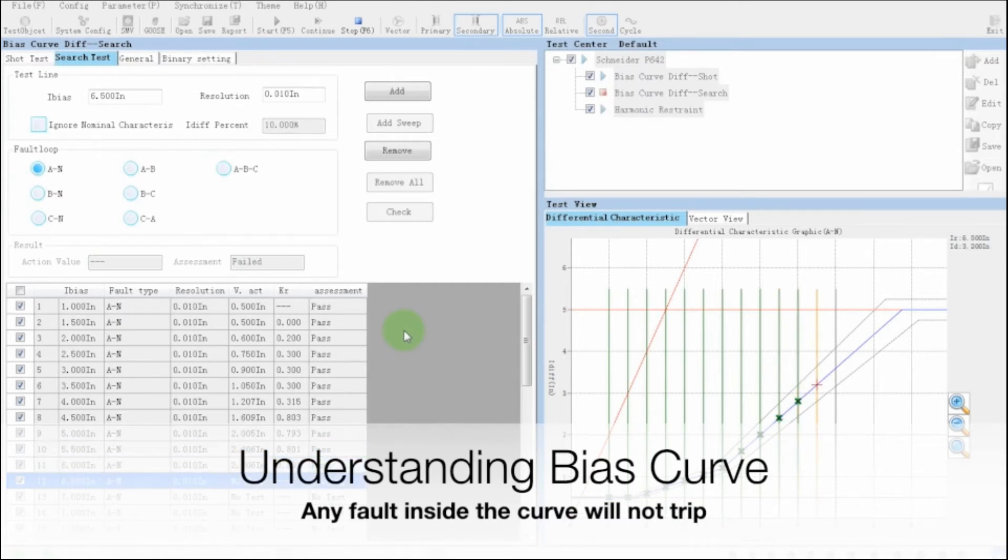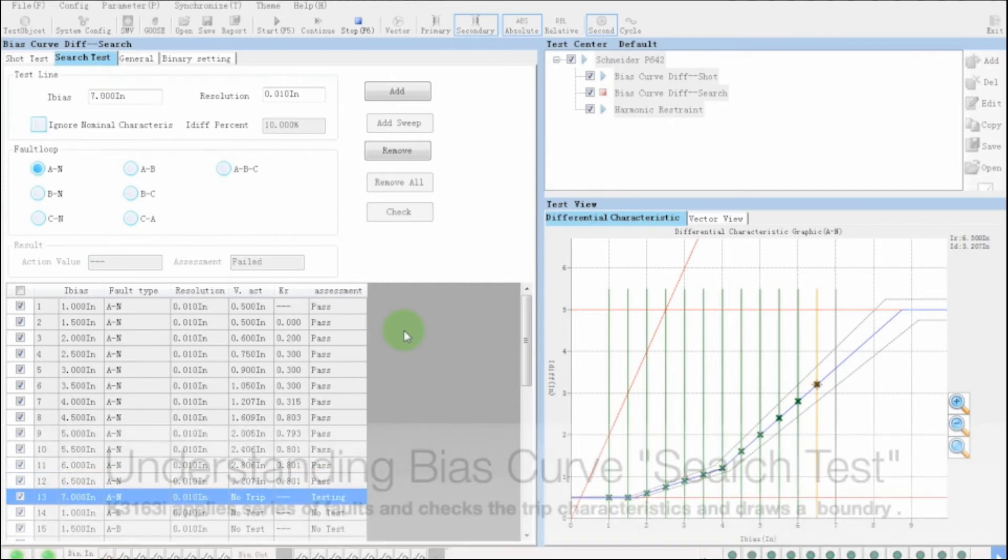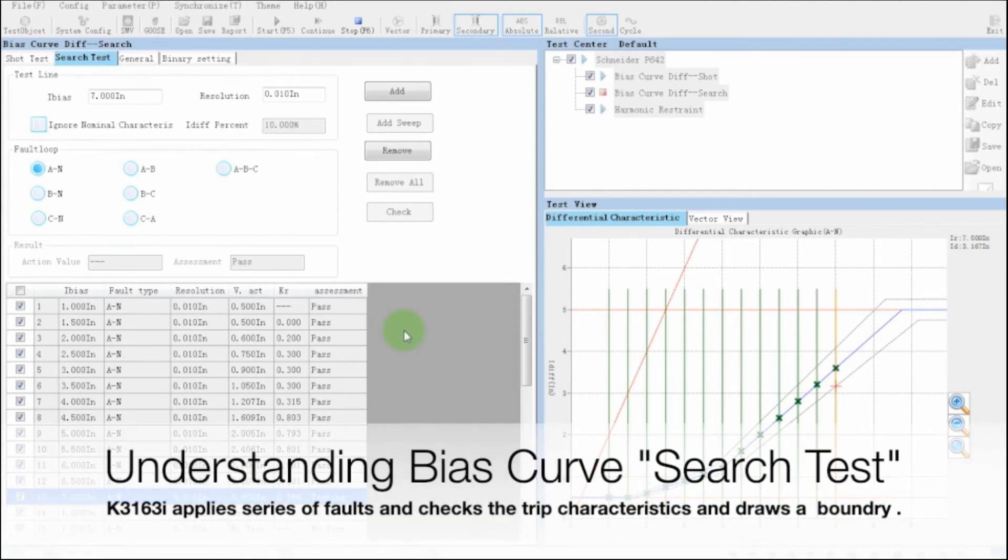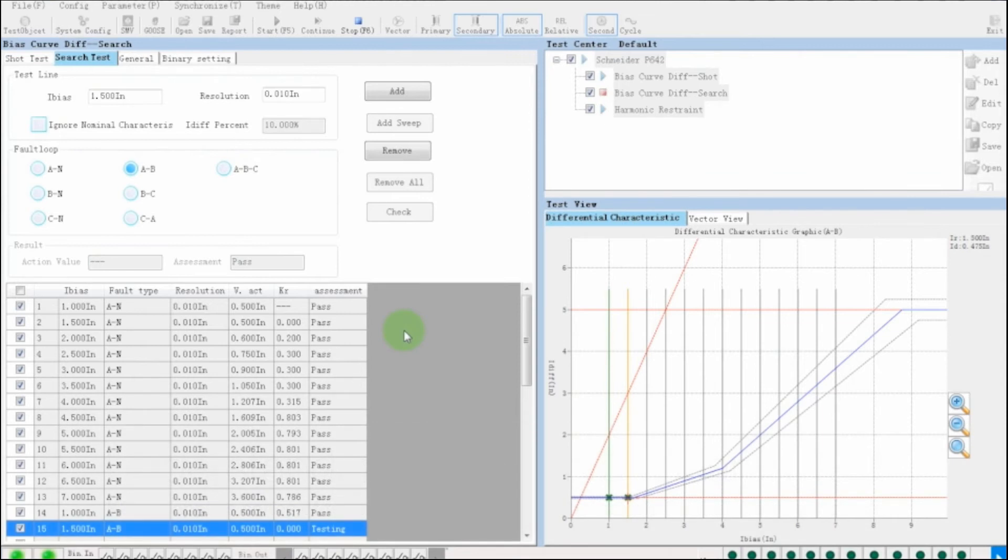In bias curve search test, K3163i applies series of faults and internally examines the tripping and restricting characteristics. Based on that, software draws the boundary of the bias curve. We can apply all types of line-to-line and line-to-ground faults during the test.